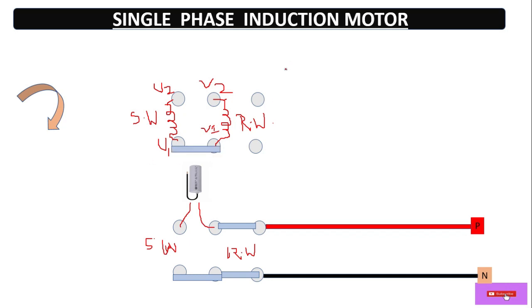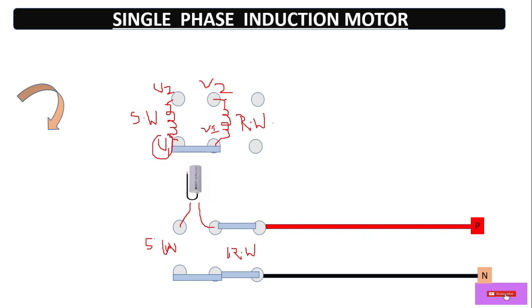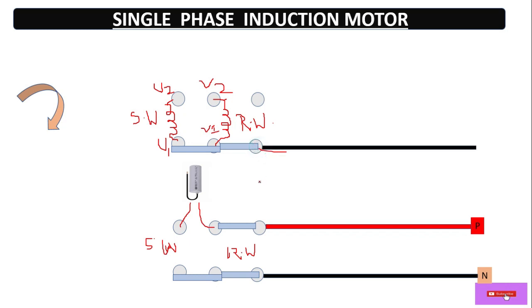To make the connection of this single-phase induction motor, we make it short to create a common terminal — V1 and U1 connected together with the help of this strip. This is one terminal of the starting winding and one terminal of the running winding, shorted to make the common terminal. At this common terminal we provide the neutral supply.